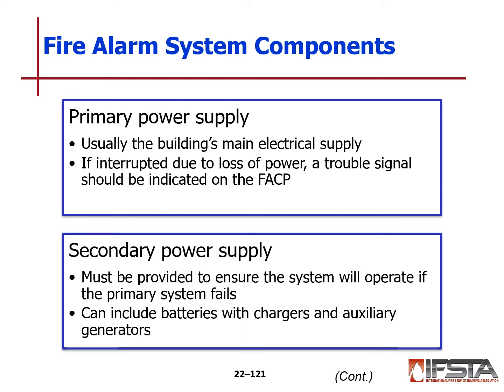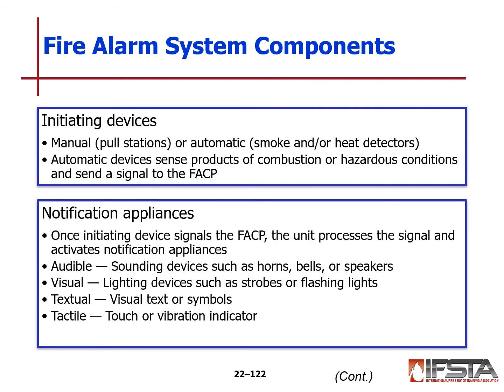Your secondary supply must be provided to ensure the system operates when the primary electrical systems fail. Again, this usually includes batteries with chargers, or it could also be auxiliary generators. Initiating devices: this could be your manual pull stations or an automatic smoke or heat detector. Automatic devices sense products of combustion such as smoke or heat or hazardous conditions, and then send a signal to the panel.